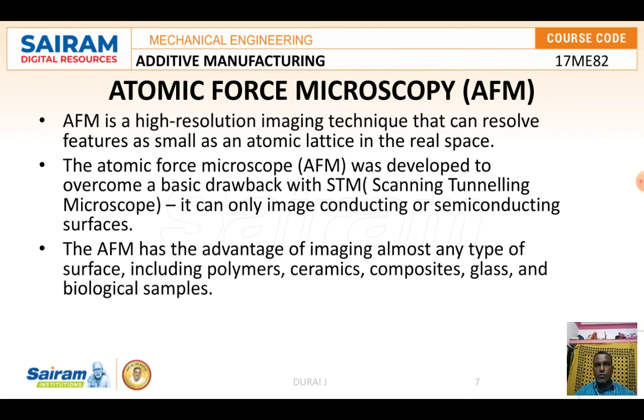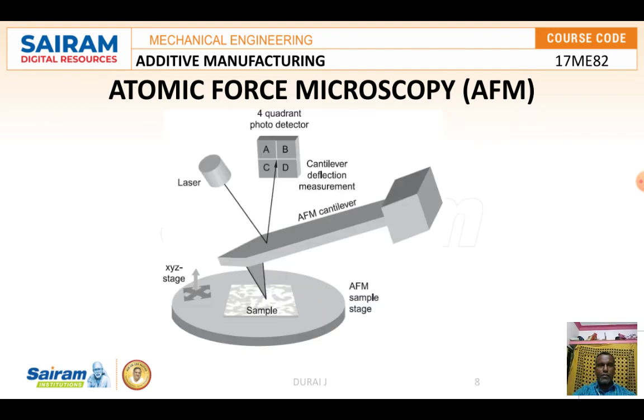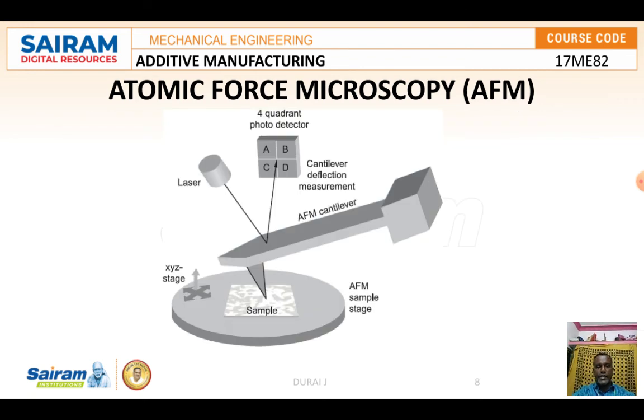In the feedback loop of atomic force microscopy, laser deflection controls the tip position, as in the figure. The laser is reflected from the back of the cantilever, which includes the AFM tip. As the tip interacts with the surface, the laser position on the photodetector is used in the feedback loop to track the surface for image measurement.